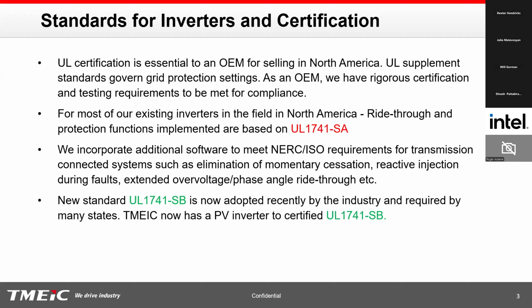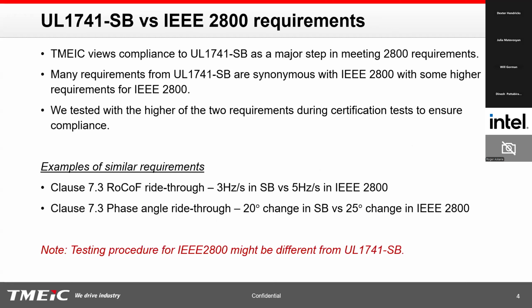Moving forward, in the last year or so, the next version of the UL 1741 standard has been adopted by the industry. So we now have compliance to UL 1741 SB, and we have our inverters certified to this new standard, which requires certain modifications in firmware as well as hardware, but our next generation inverter is compliant to this 1741 SB standard. The reason I'm telling you about all this is because we view UL 1741 SB as a major step in meeting 2800 requirements. A lot of requirements in this SB standard are synonymous with 2800, not necessarily the same, but on a very similar line.